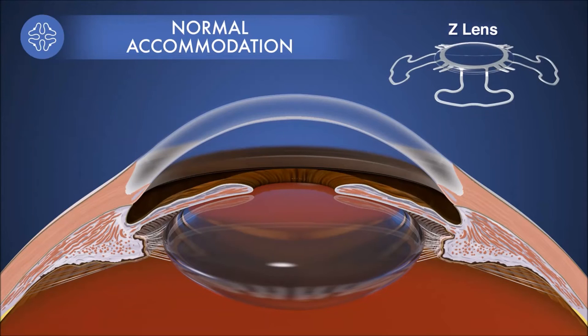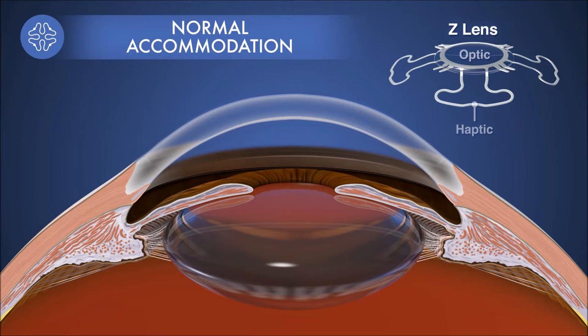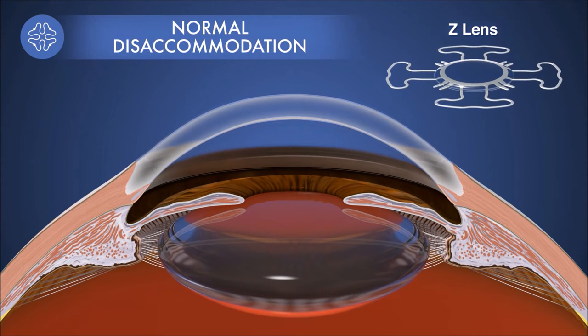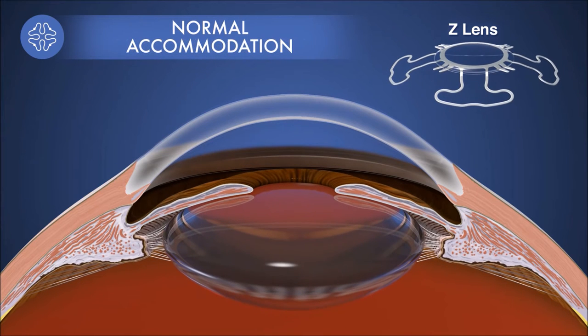Our Z-lens intraocular lens is built to mimic this movement. In the Z-lens resting state, the optic is vaulted forward by haptics that are angled backwards. As the ciliary body relaxes, zonules pull the haptics flat, moving the optic backwards. When the ciliary body contracts, the haptics vault the optic forward.